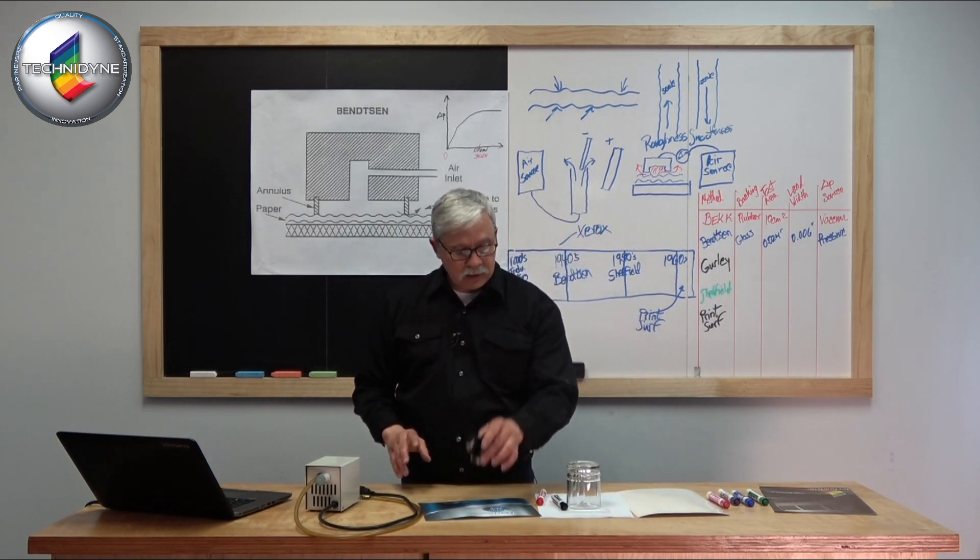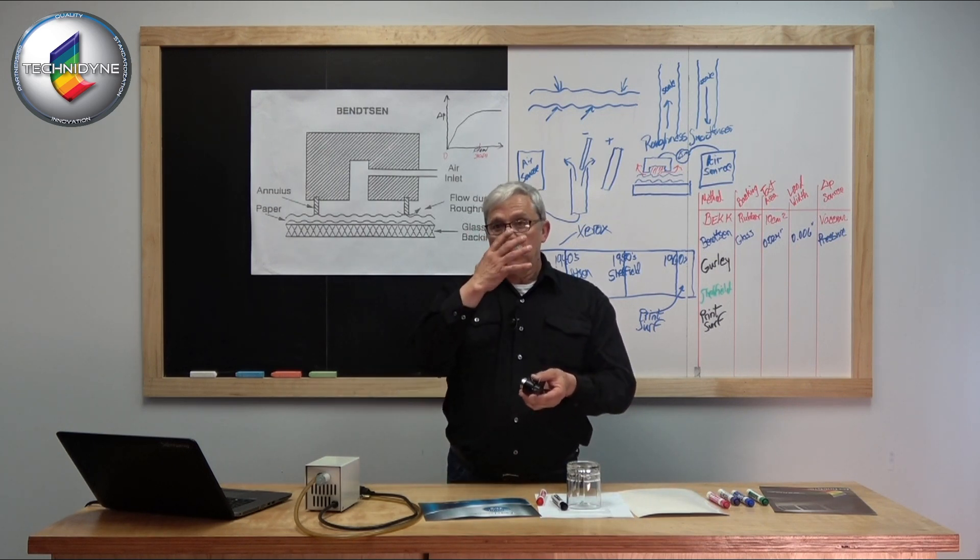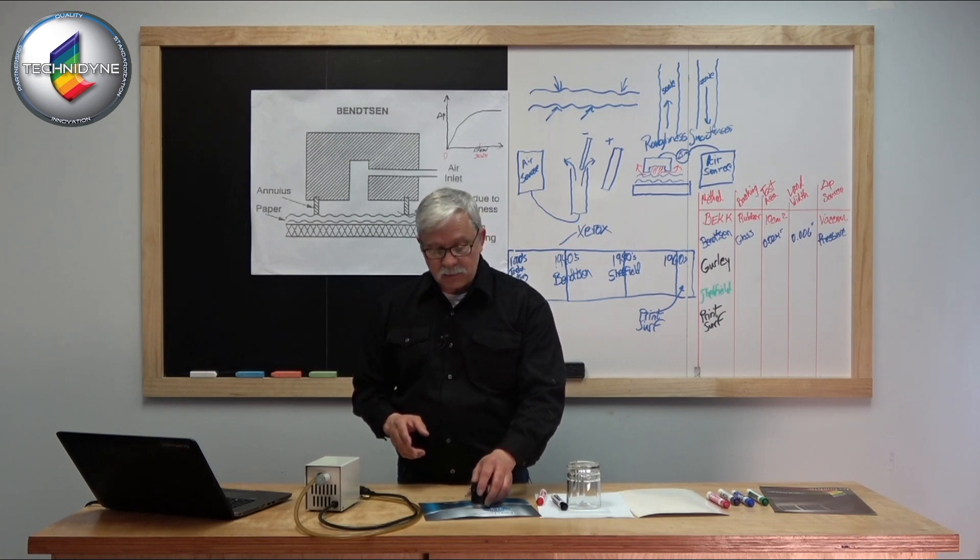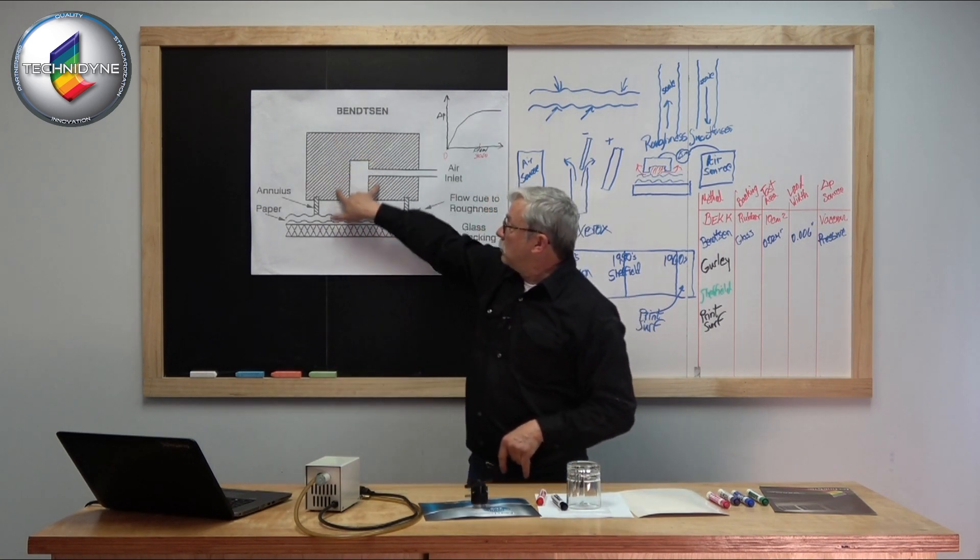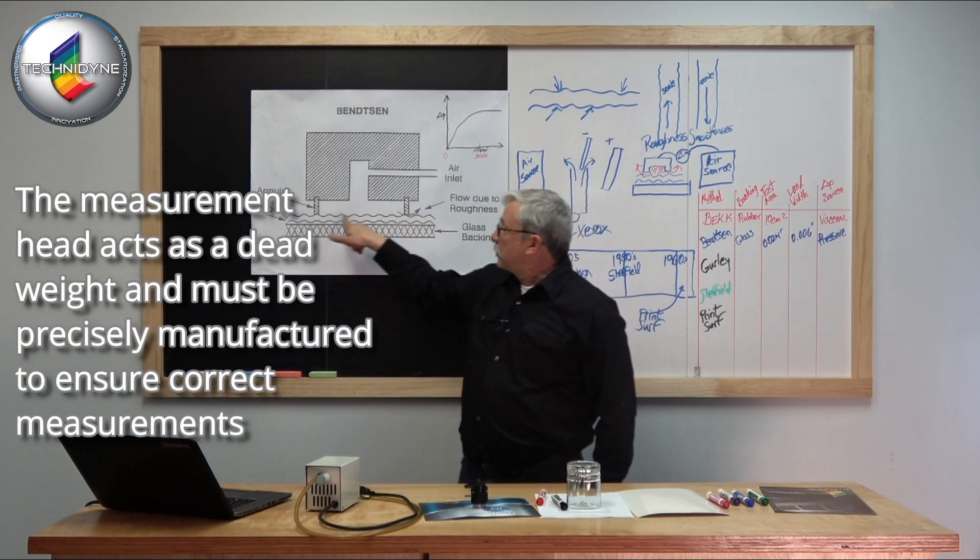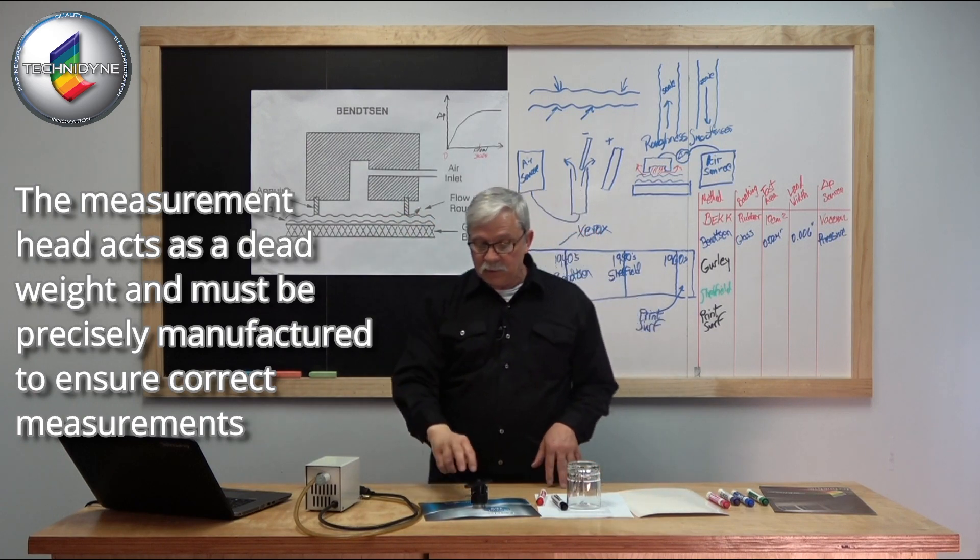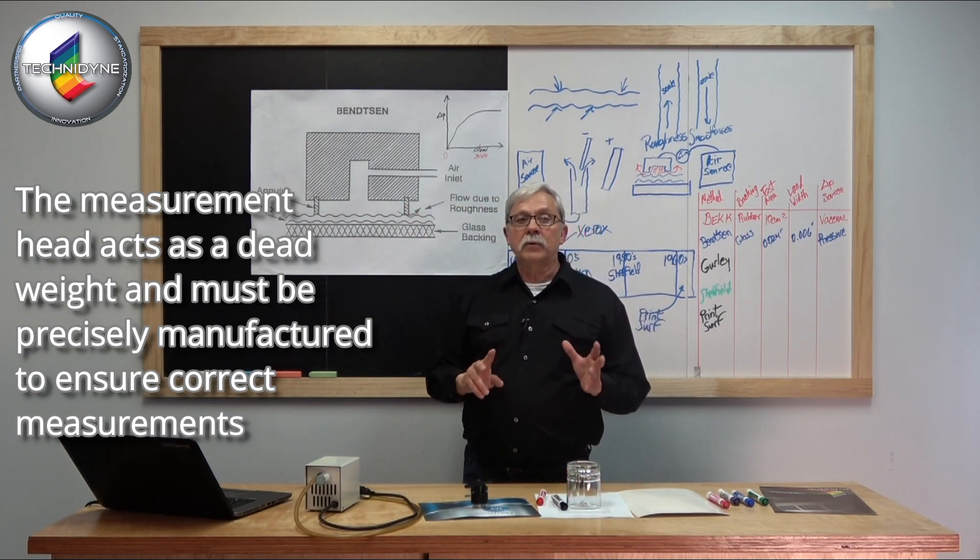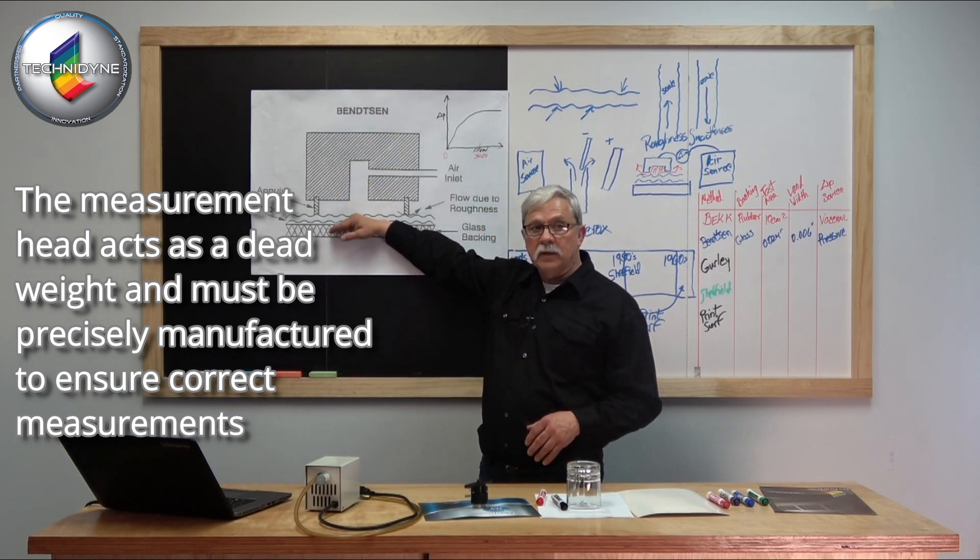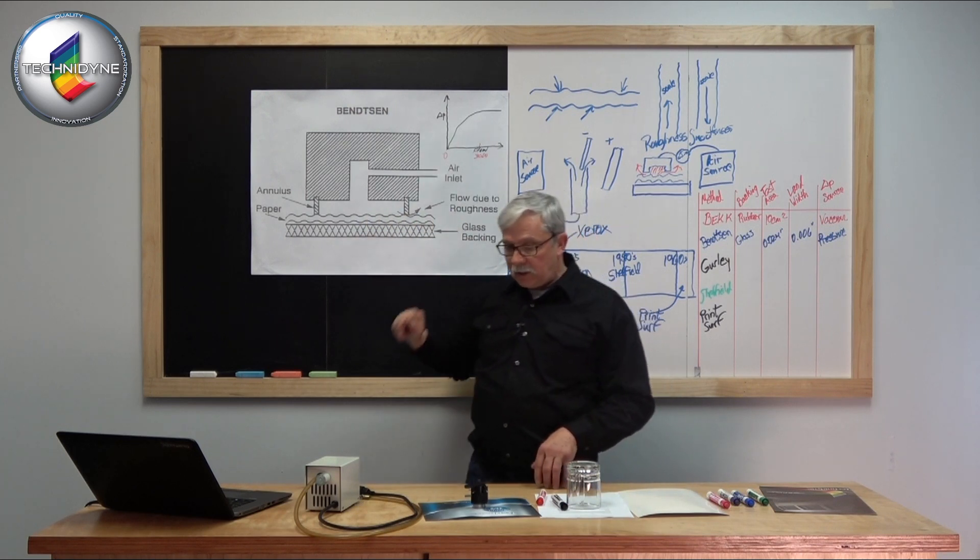You could imagine that if I had two different masses, if I had one at 260 grams and another at 460 grams, placing that on the sample would exert more pressure on the paper. I may do some smoothing or compressing if the sample is compressible. Now I'm introducing a variable from my first piece to my second based on loading the sample differently. So I have to maintain my loading pressure, my air inlet pressure, and how flat the surface is, along with how flat my backing is.